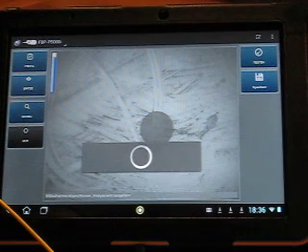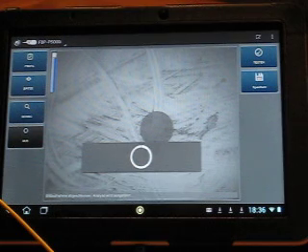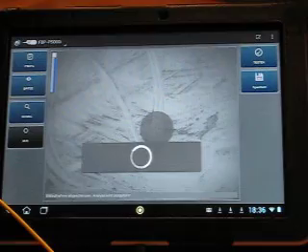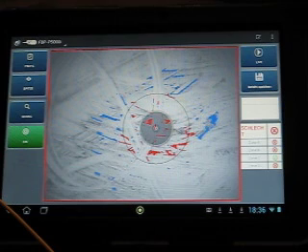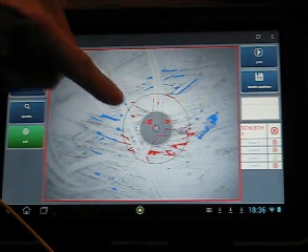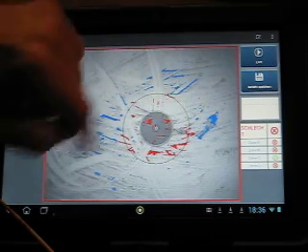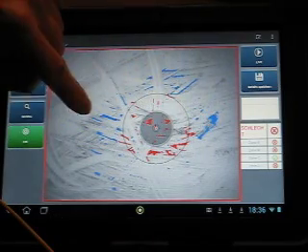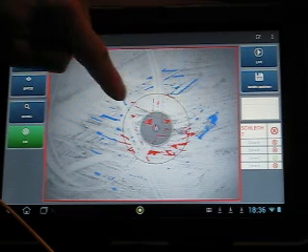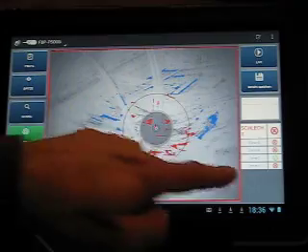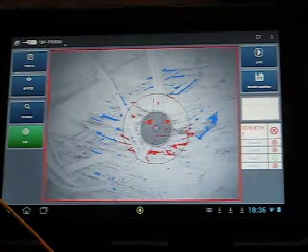It takes a while. The software is investigating the size and number of damages and dirt on the fiber surface. And finally gives you a report. This is a quite dirty connector. I have an indication of red dirt, red marked, blue marked means it's detected but it's not so severe. Red means it's severe, the reason why this connector fails.